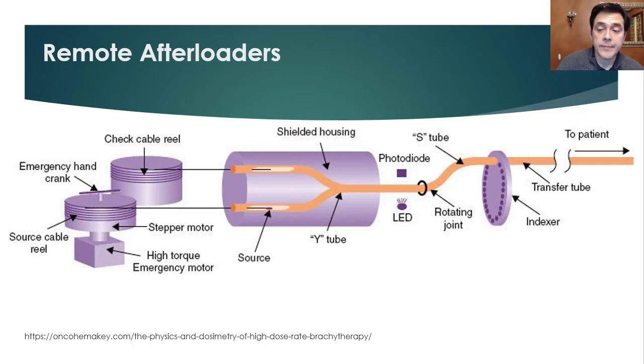So in diagram format, here is the transfer tube that exits from the face of the applicator. Here is the transfer tube that exits to the face of the indexer. Same transfer tube. The indexer has an S-tube pathway, so there's no straight path going to a rotating joint. The rotating joint selects which one of the channels the source is going to go through. There is some sort of positioning system that counts the amount of distance and reflections on the cable, in this particular model, an LED with a photodiode, to show that the source is out in play or the dummy check cable is out in play.